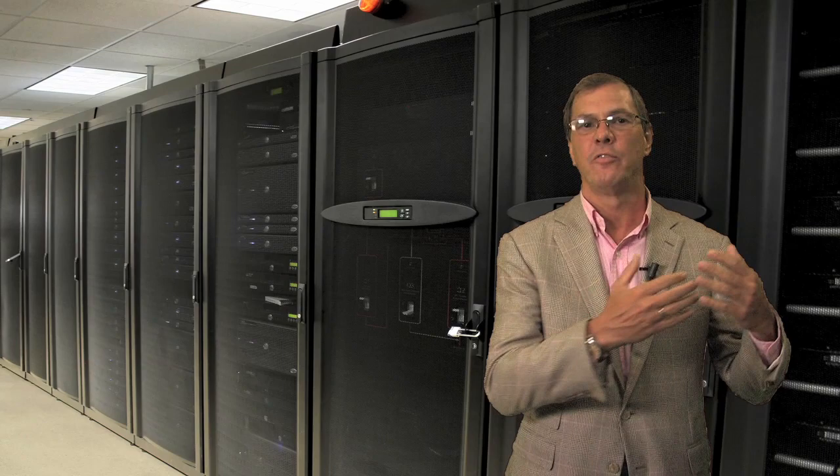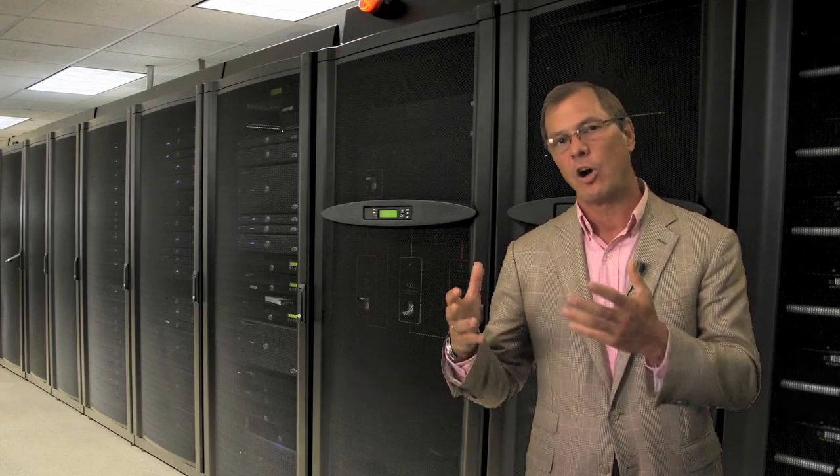Most people, when they consider the possibility of facility modules, naturally assume there will be savings in time and savings in cost. But one thing people don't appreciate that we believe is very important are the possible reliability improvements. Specifically, we know that many of the kinds of failures or problems we experience in actual data centers are not caused by the devices that are used, but were caused by a mistake made during the installation or the interconnection of those devices.